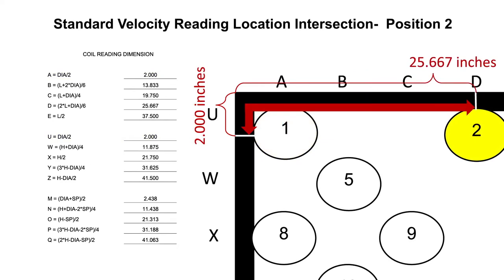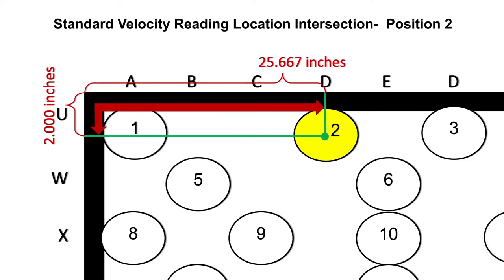The standard velocity reading location for position 2 is at the intersection of D and U. The value for D equals 25.667 inches and the value for U equals 2 inches. A measurement and marking for D is 25.667 inches from the left towards the center horizontally, and for U, 2 inches from the top towards the bottom. Therefore, the position 2 standard velocity reading location is at the intersection of D, 25.667 inches from the left to center, and U, 2 inches from top to bottom.